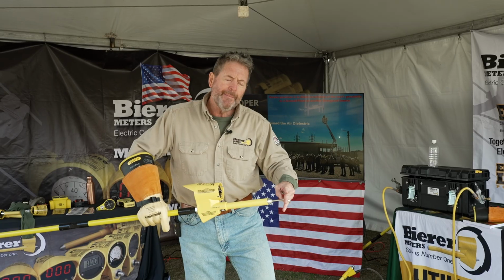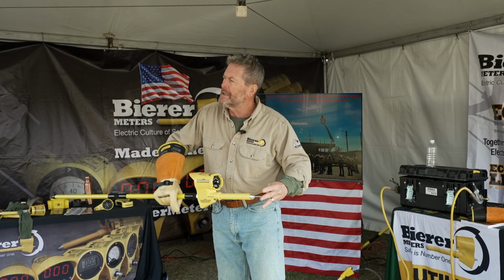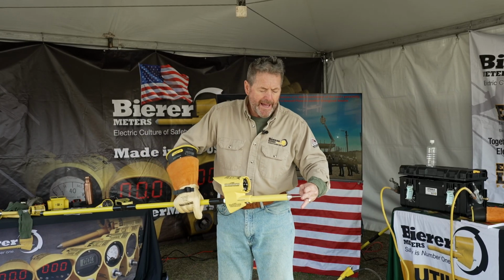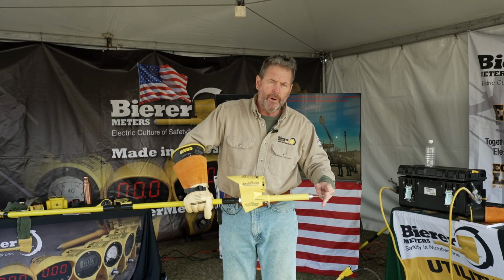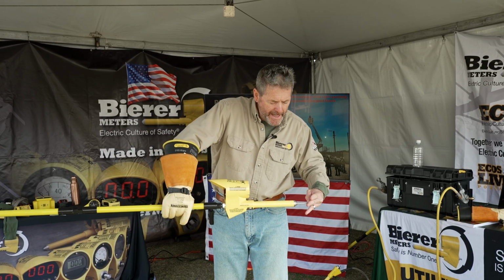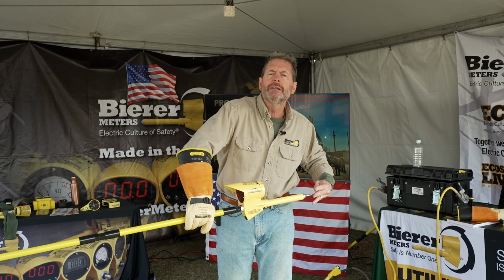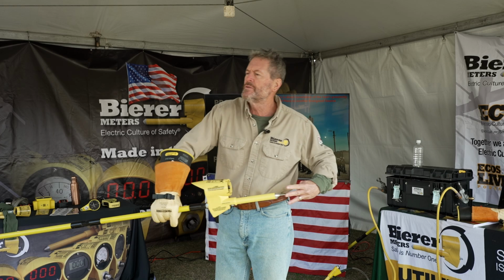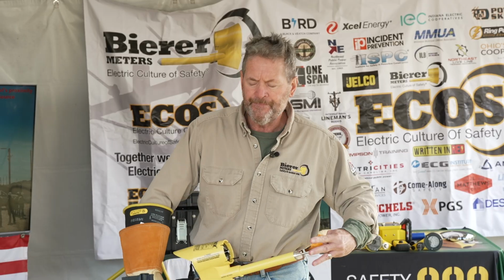So, if I'm at this long source and I start bringing the meter, I don't have that 90 degree, I'm not perpendicular to that same long source, and I start bringing that meter where it's parallel to that long source, what happens to the numbers? Well, you get closer and closer to the same potential. So your numbers will go down. Absolutely.